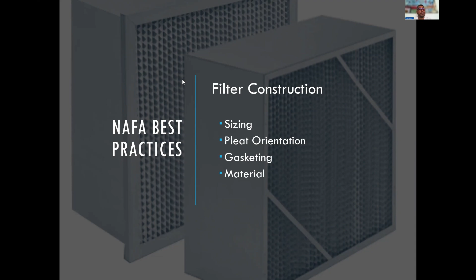One thing that actually refrains us from doing that could be the high velocity of speed in equipment. And what manufacturers have put together is changing the pleat orientation. So if we're looking at the screen here, we see on the left-hand side, we have a 20 by 25 by 2 filter, and those pleats run vertical. Now the same filter also horizontal. Now the pleats are running horizontal. So knowing when to use a reverse pleated filter versus a standard pleated filter in the different types of equipment can have a great impact on how that filter holds up with higher CFMs.